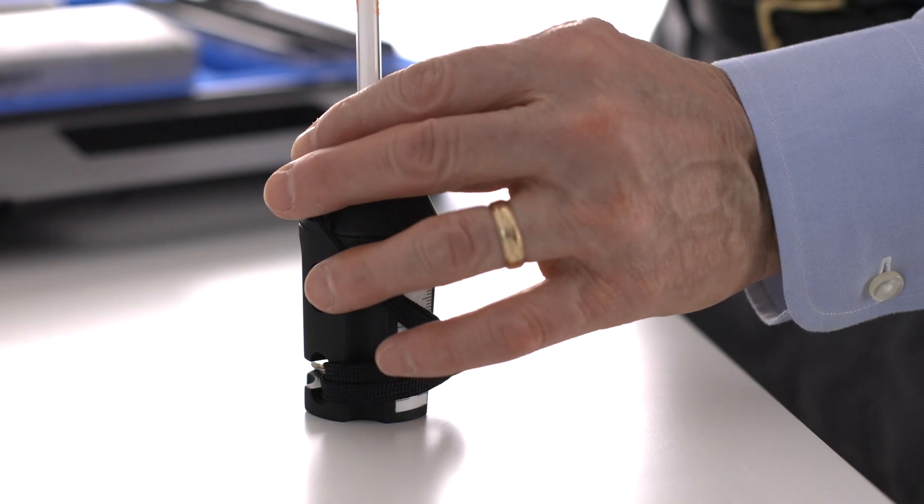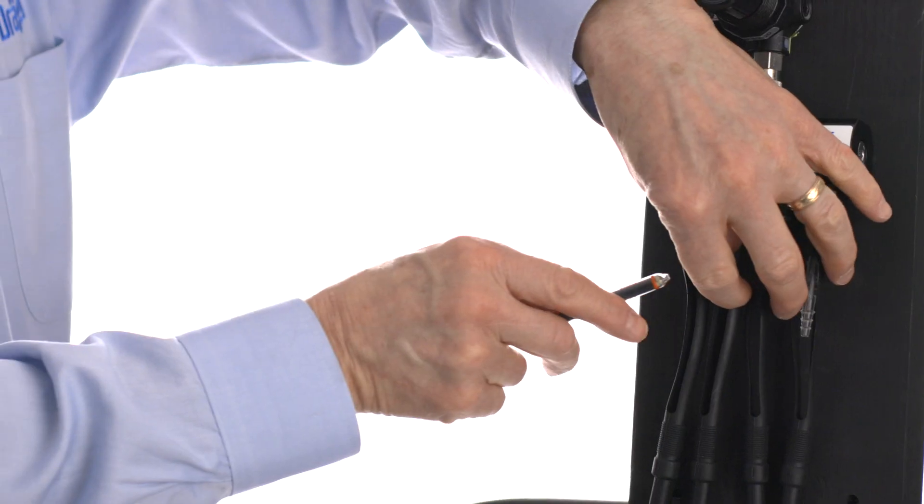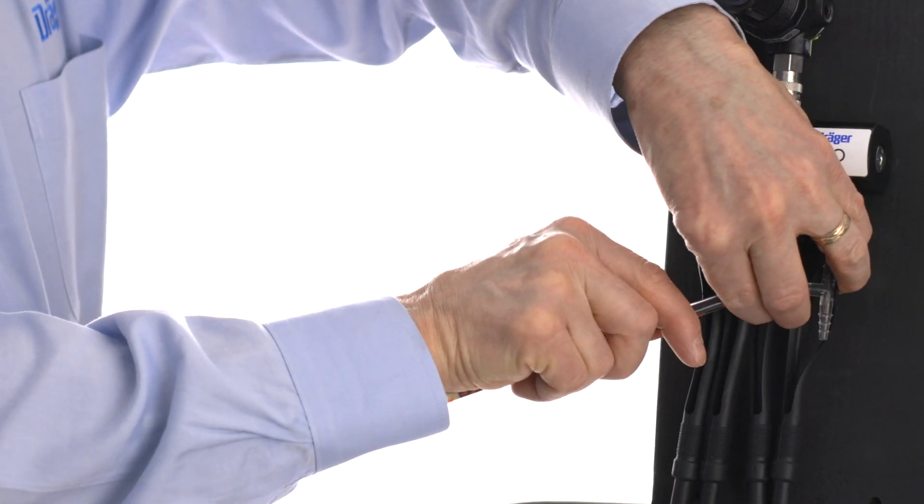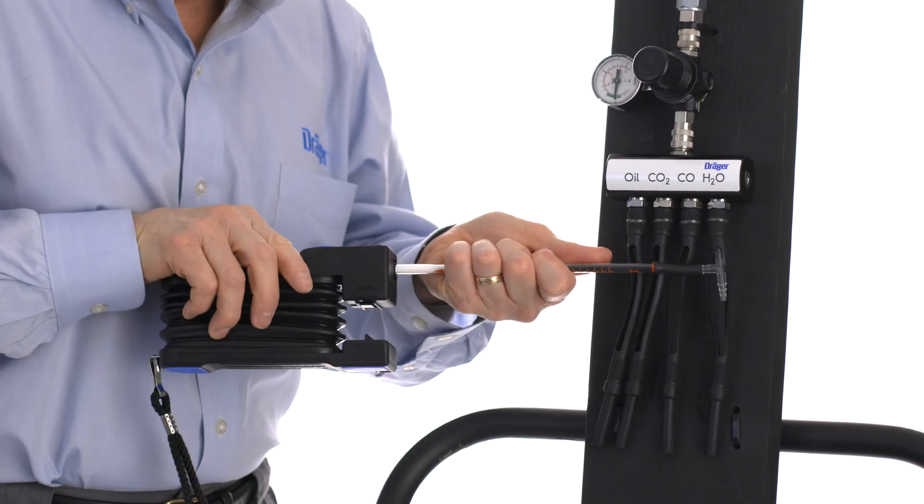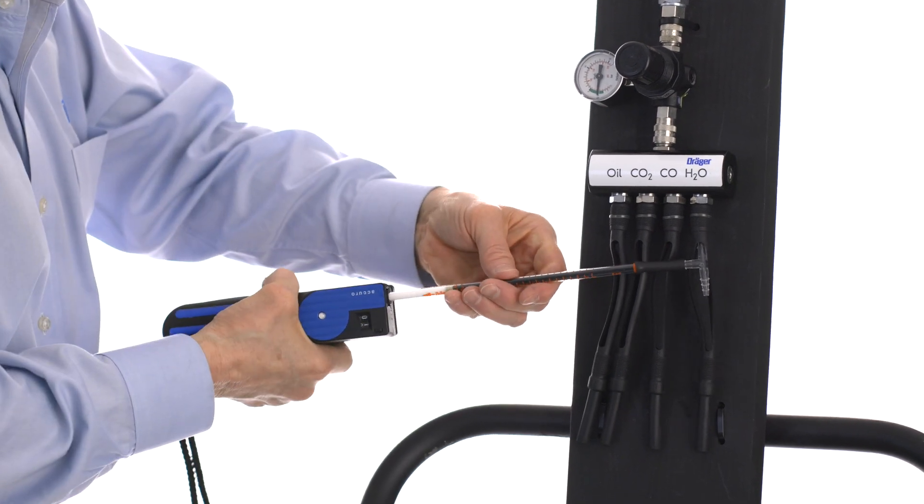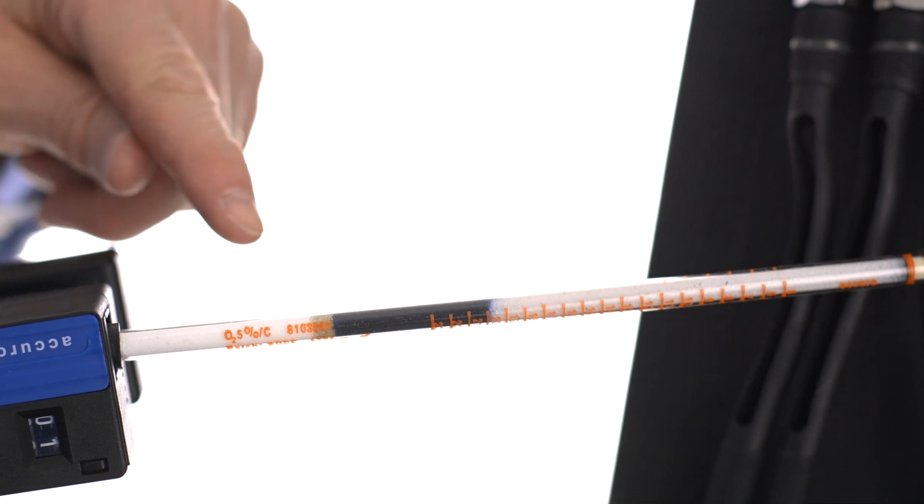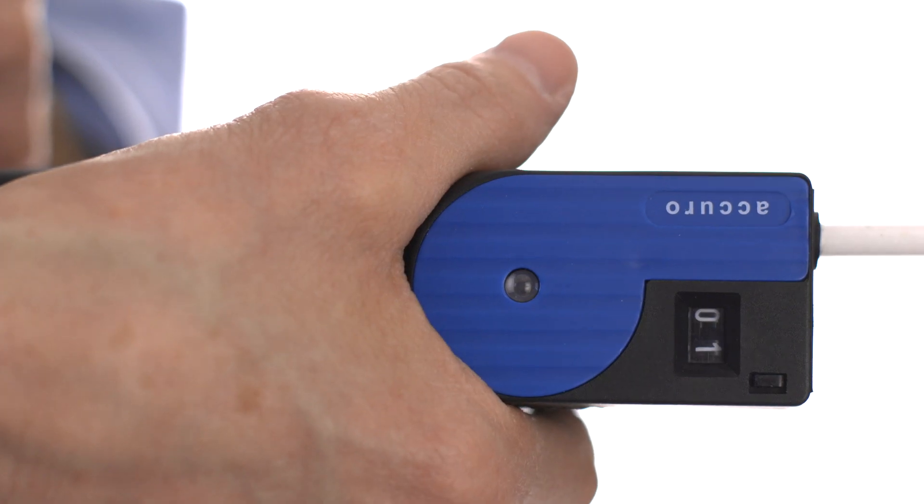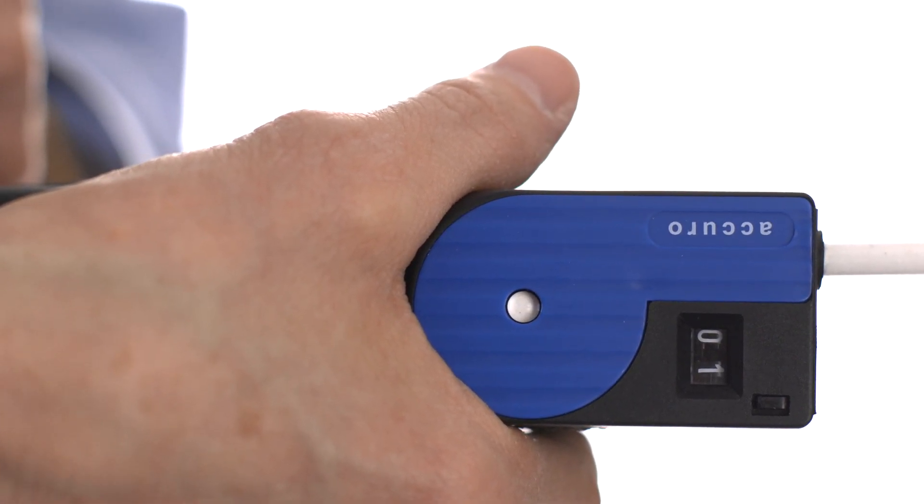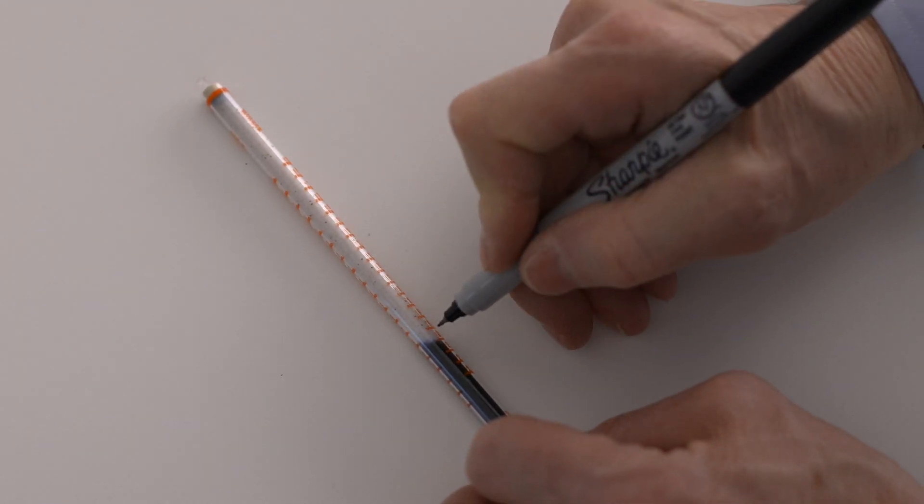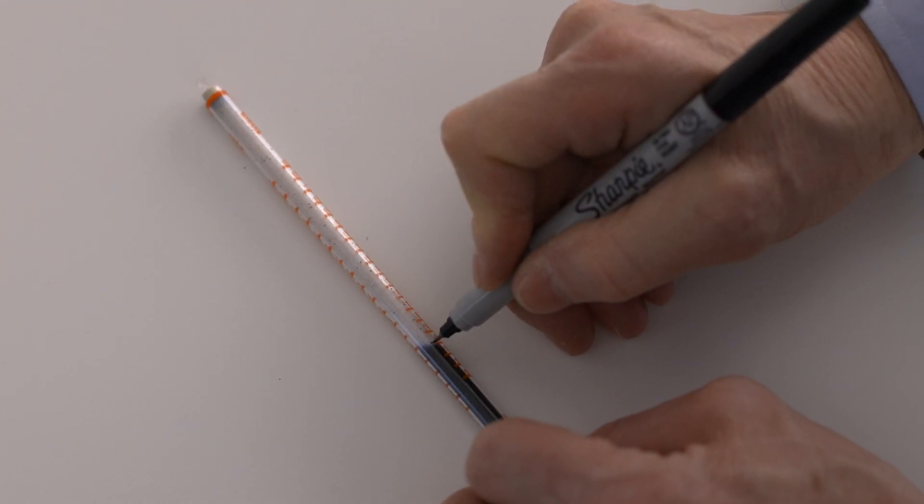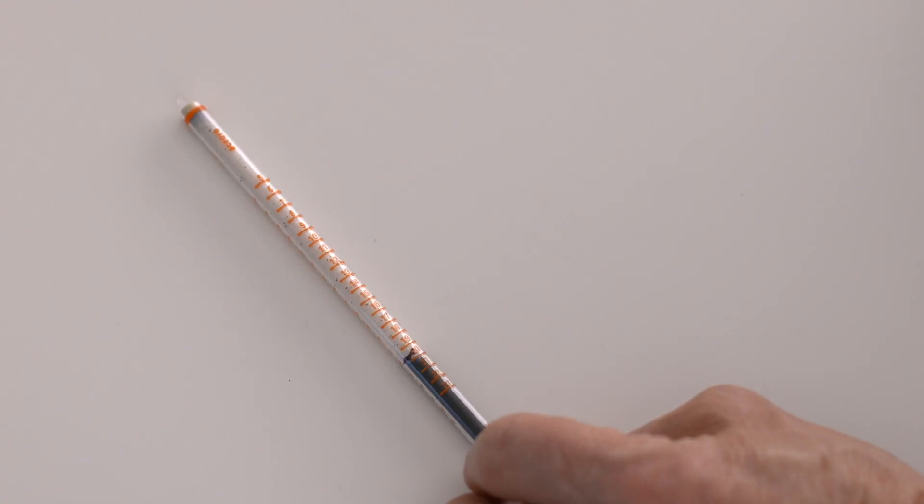Remove the tips of the oxygen tube. Immediately connect the tube and the Acuro and take a reading by completely compressing the pump. Exercise caution as the oxygen tube will become quite hot. At the end of the stroke cycle, read the tube immediately. Oxygen reads to the midpoint of the change in the discoloration. We will be using the Acuro scale. This reading is 19.8 volume percent oxygen.